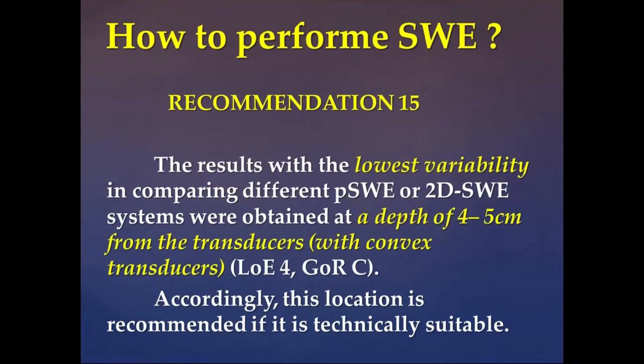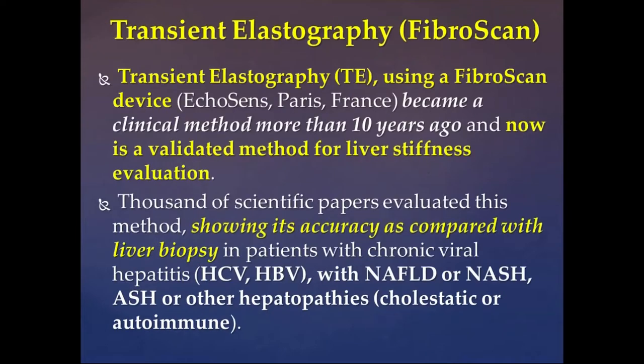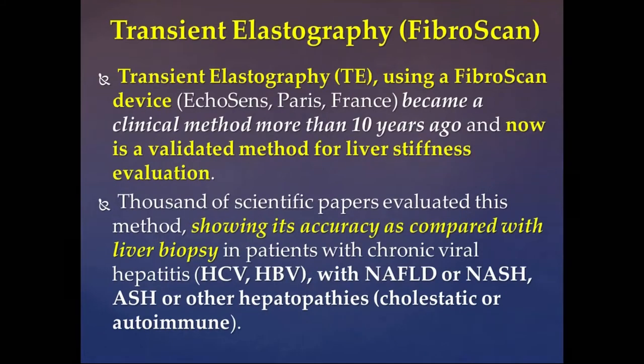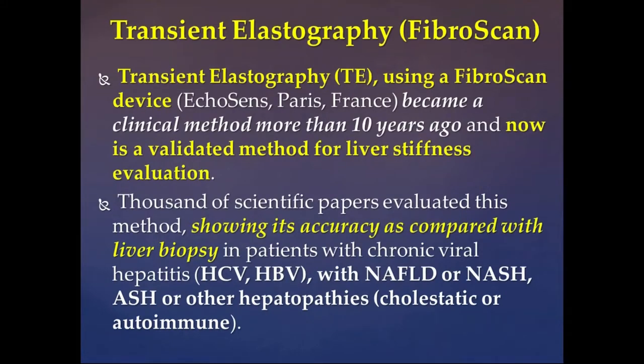Recommendation 15: for reliable measurement with lower variability, place the box at a depth of four or five centimeters from the skin or transducer surface. So we measure four or five centimeters from the skin, and also ensure more than one centimeter below the capsule.